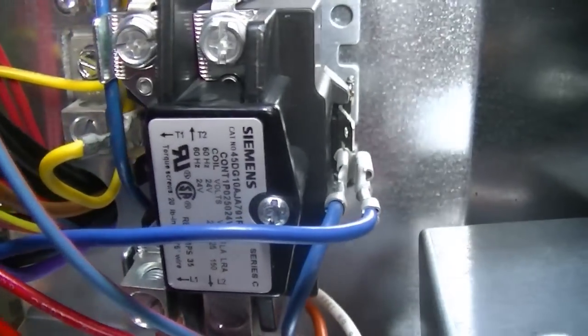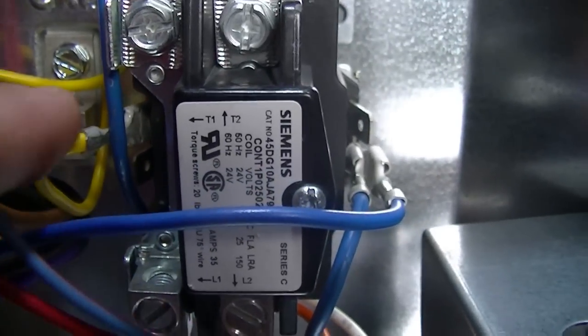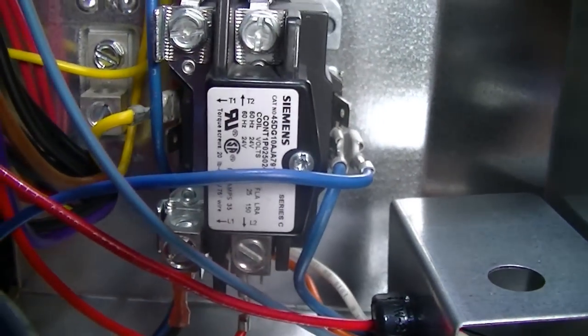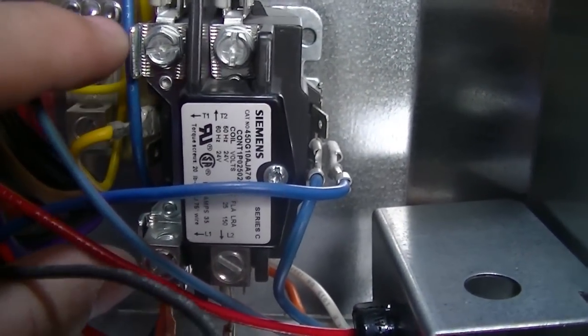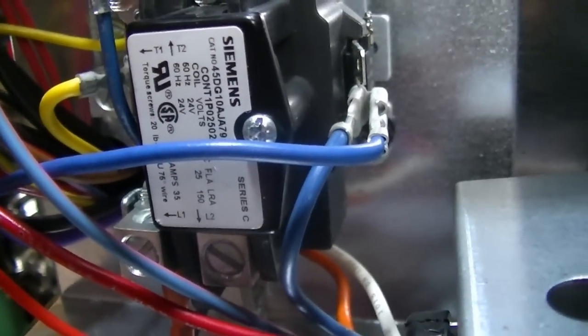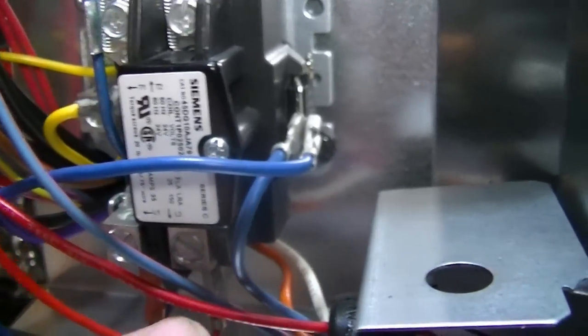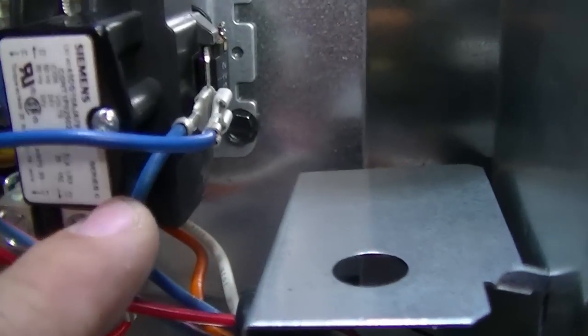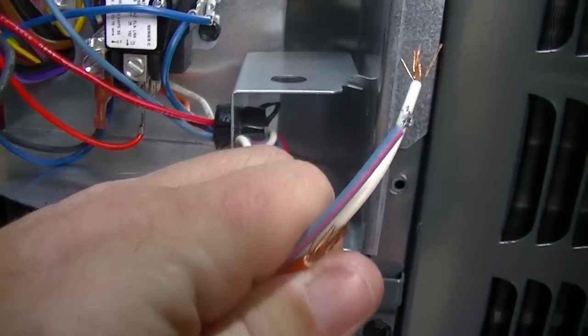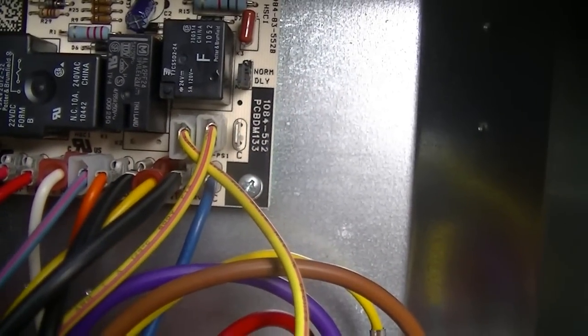On either side of the contactor, there's low voltage wires. We have one yellow here, two blues on this side. Sometimes on the contactor, they'll both be on one side. The Honeywell was like that. The blues on this side are common, common side of 24 volts. One of them is running directly out to the field wiring here. The other one is going all the way up here to the defrost control board.